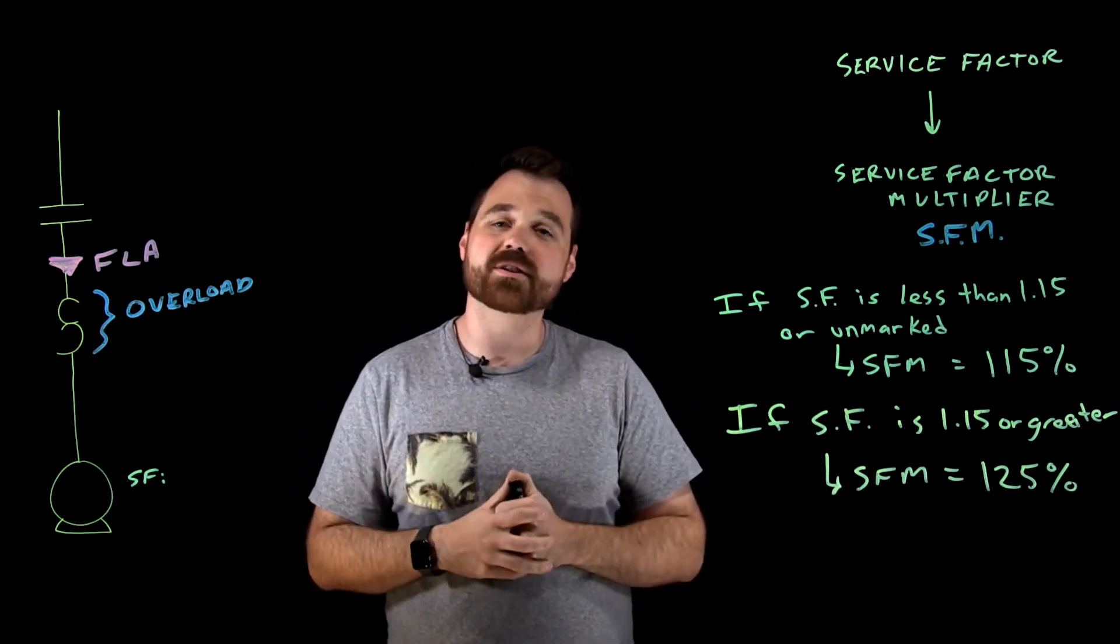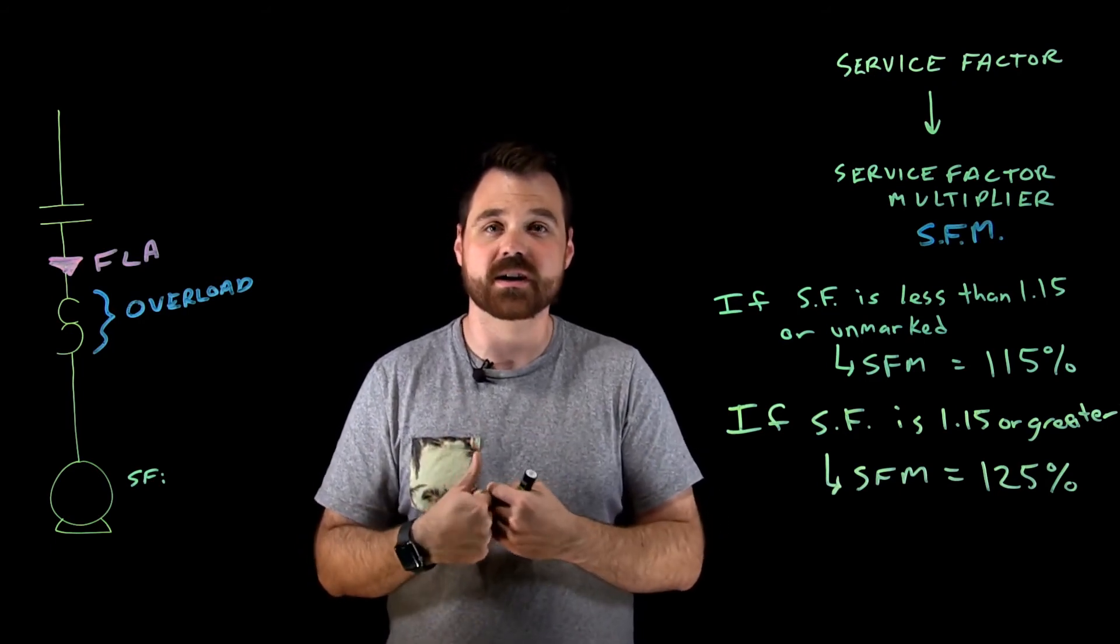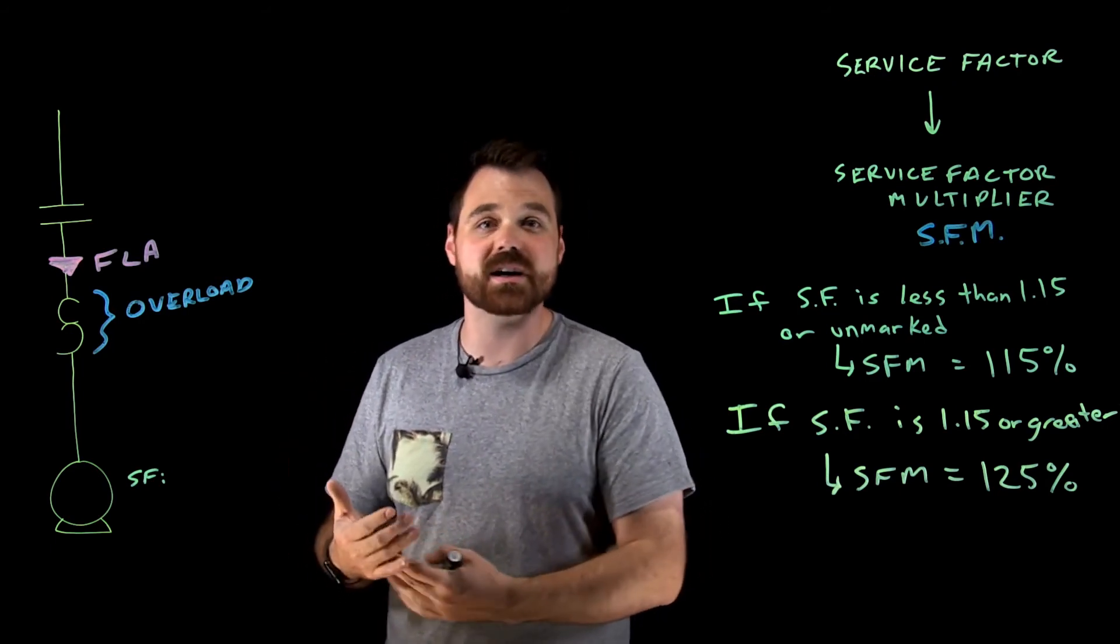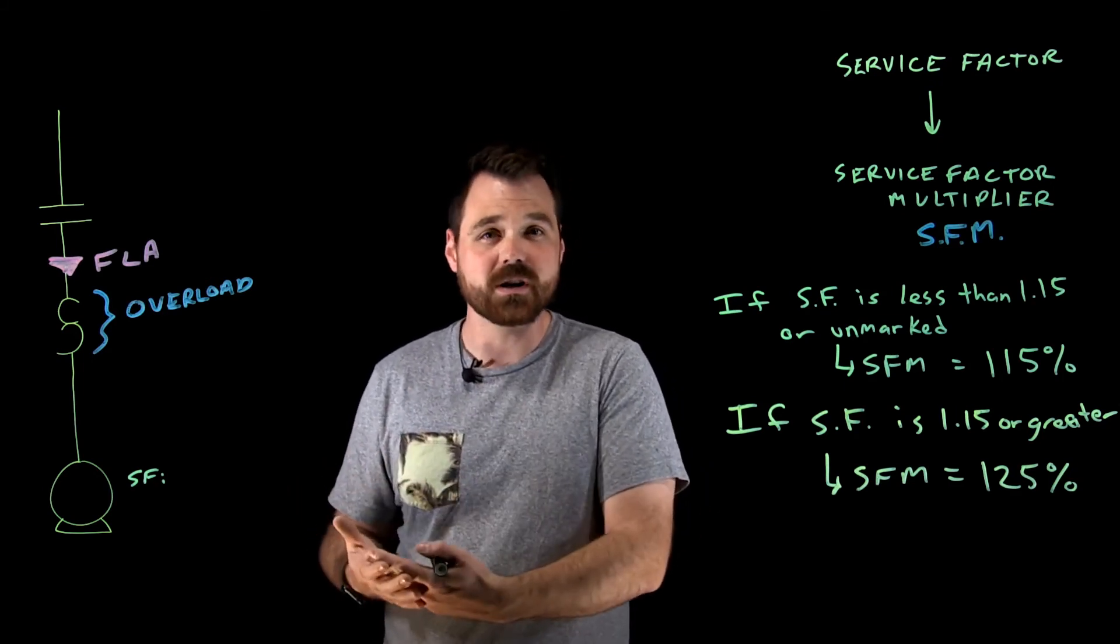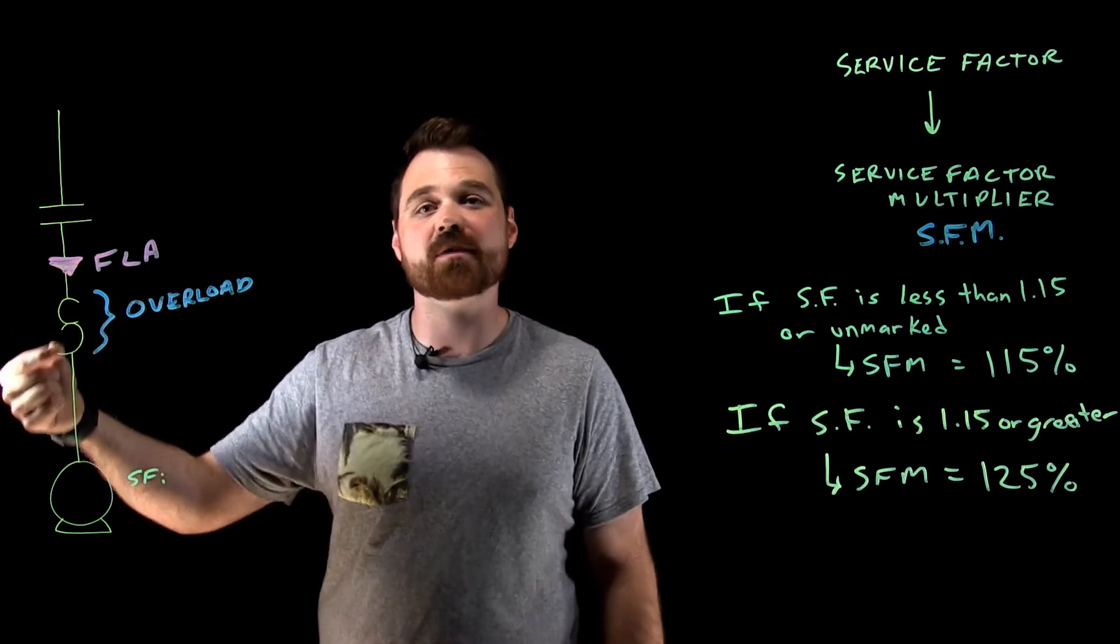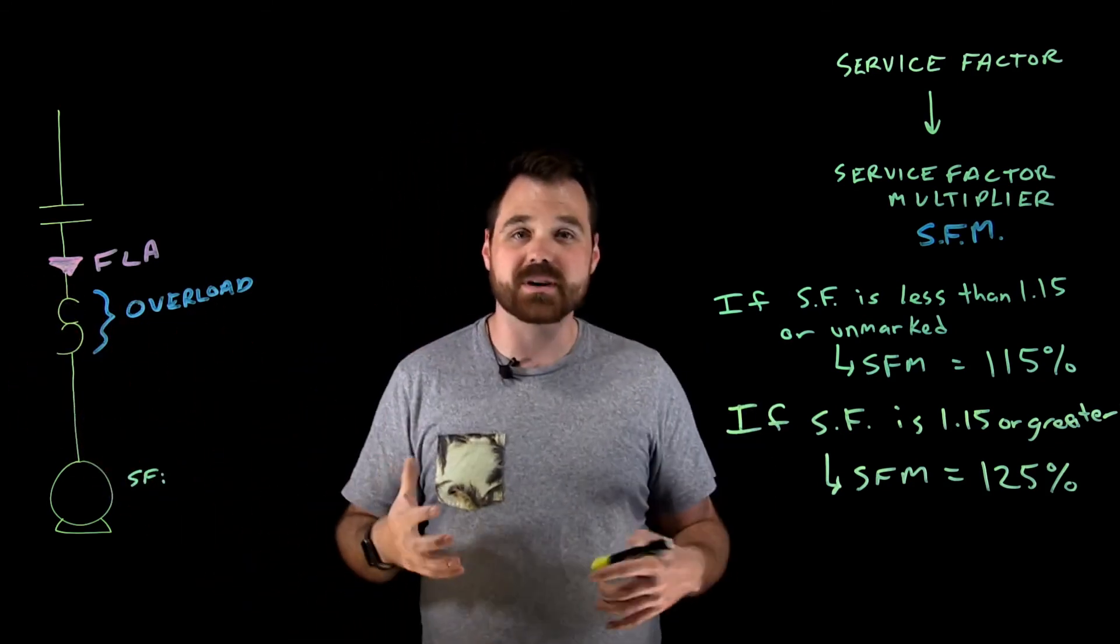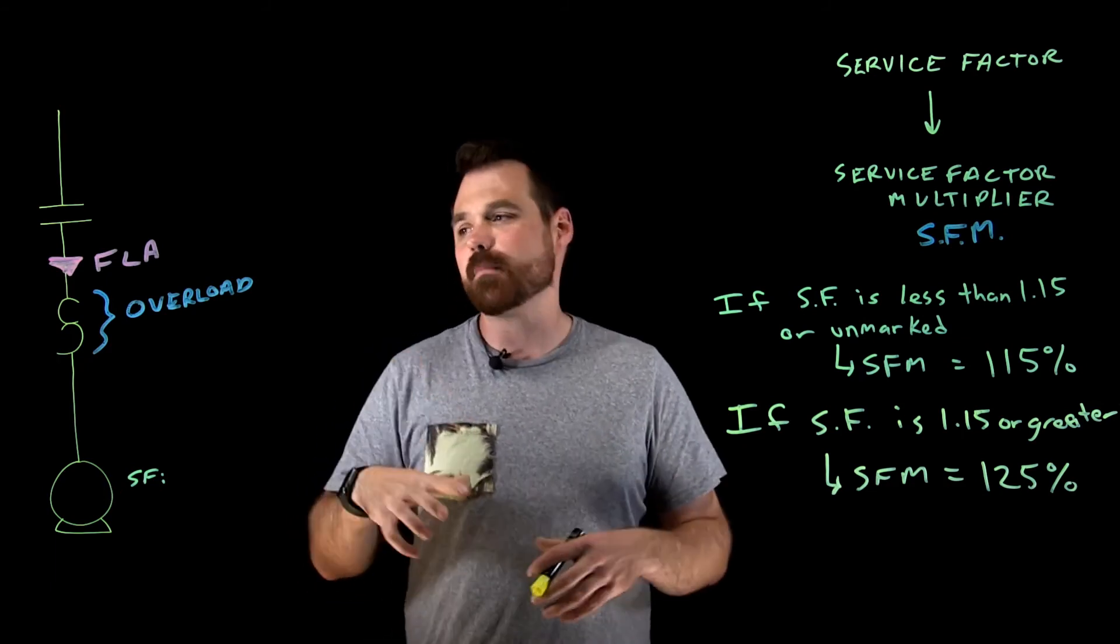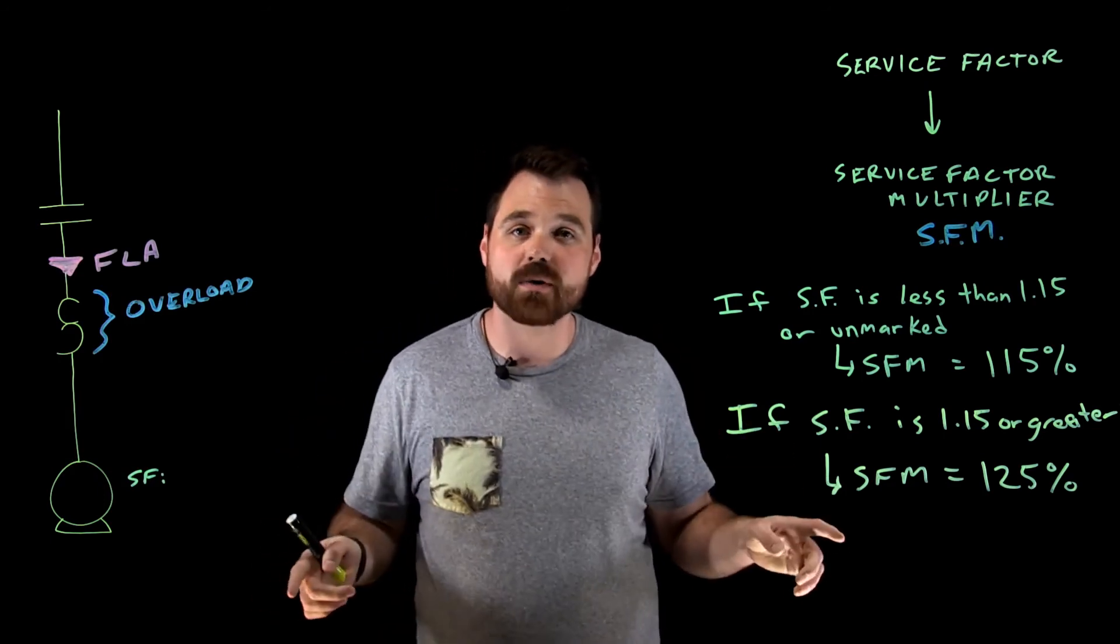Now, one really important thing to remember here is if you're using some type of reduced voltage starting, something like a Y Delta or an auto transformer or a part winding starter, your overloads need to be set on whatever current is actually going to be flowing through that overload device. So if you're doing some type of special motor starting, make sure you calculate what's going to be flowing through that device. I do have a couple videos on that you can check out.